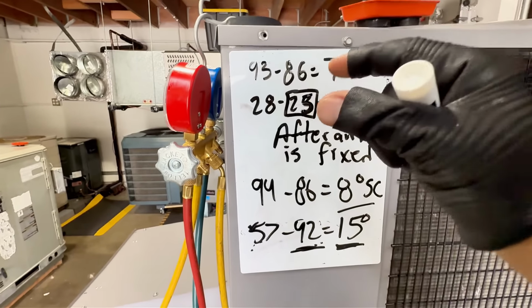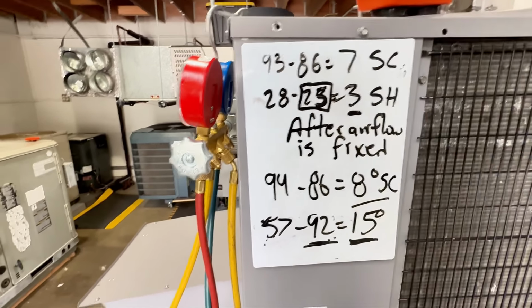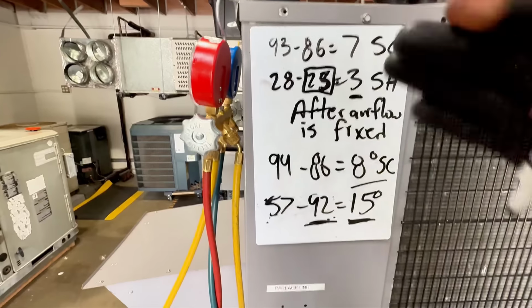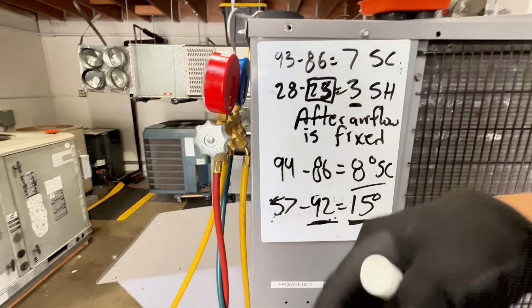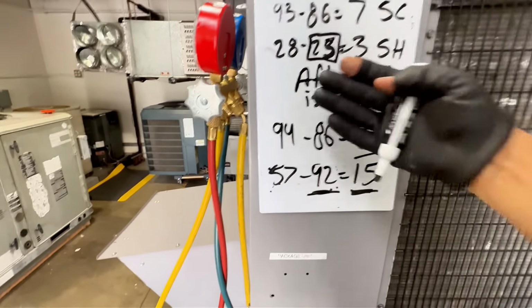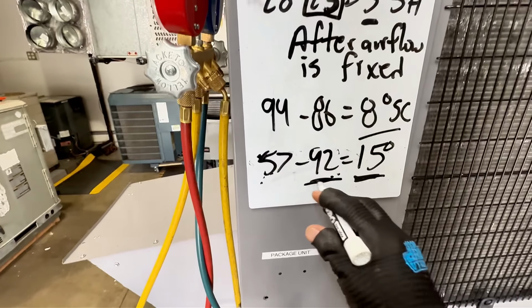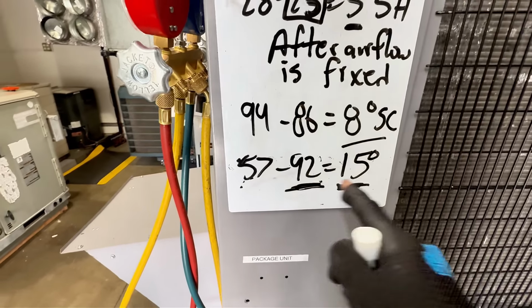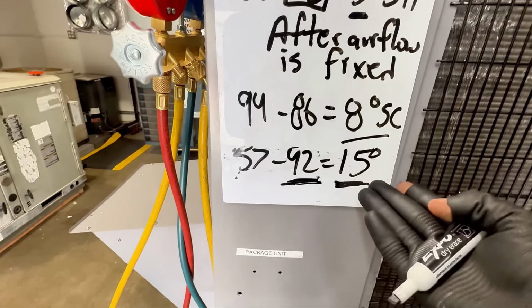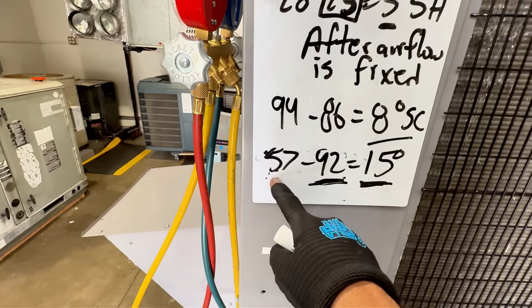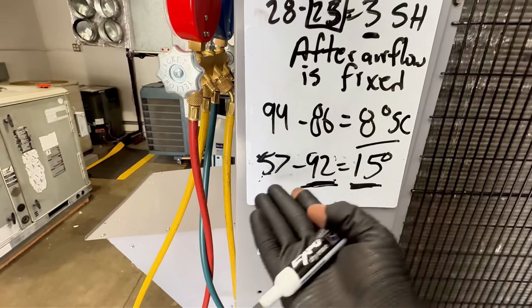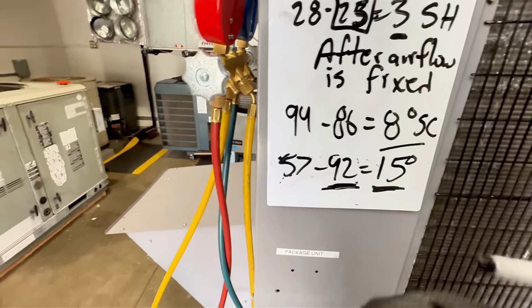The TXV is pinching, and it's going to be trying to calculate that superheat, but the evaporator is going to be super low because you're not introducing a lot of refrigerant. So once I fix the airflow, I'm above 32 degrees evaporator temperature, 15 degrees superheat. My suction line is 57 degrees. This I'm happy with. My subcool, I'm happy with too.